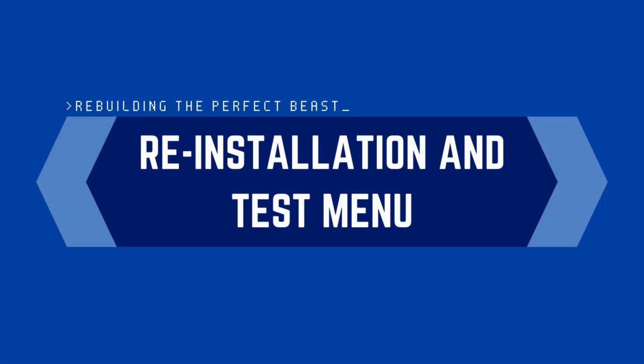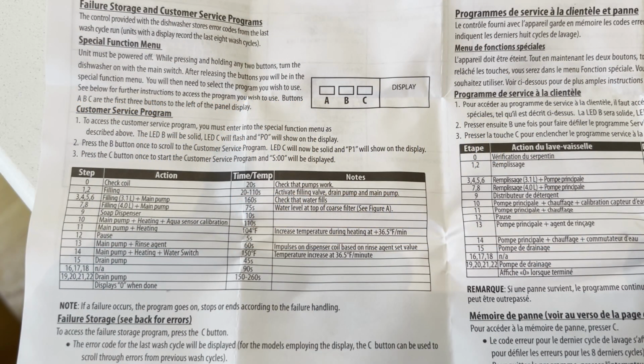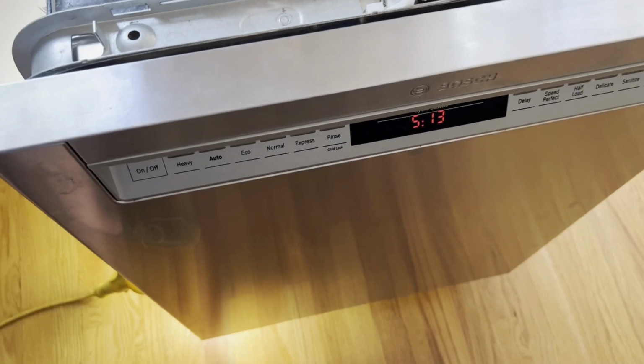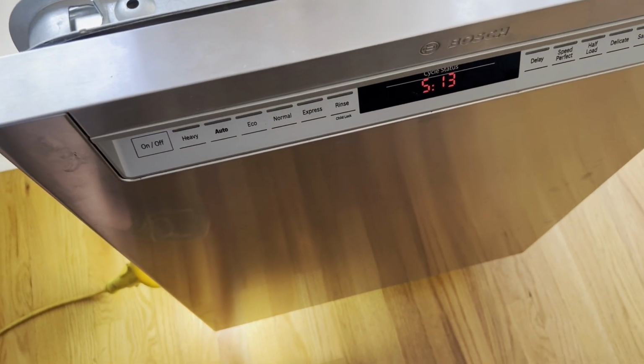Okay, success — it's installed temporarily and running through its test menu. The instructions mention a special function menu: you press key B and C while powering it up, and it displays P0, then you can run a self test that goes through all the steps to make sure everything's working, ending with a result that says it's good. You can read the instructions, but it's up to step 13 — step 13 means it's good to go.